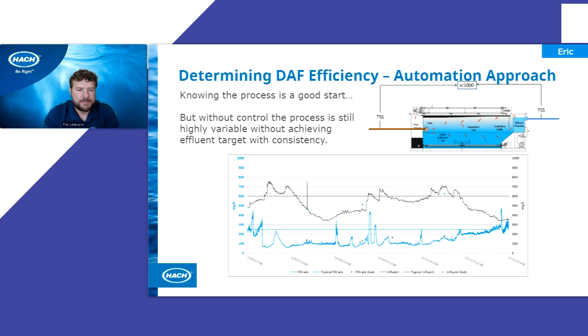grab samples. So if I can point out a few things, the dots here, on the bottom line, the blue is going to be the filtrate or the effluent. The top line is going to be the influent. And the dotted lines are the baselines or the typical operation of the DAF itself. The dots here are going to be the grab sampling points. So if we look at this one here and here, we can see as they pull the grab sample, it looks like everything's in check and it's operating as expected below the baseline.